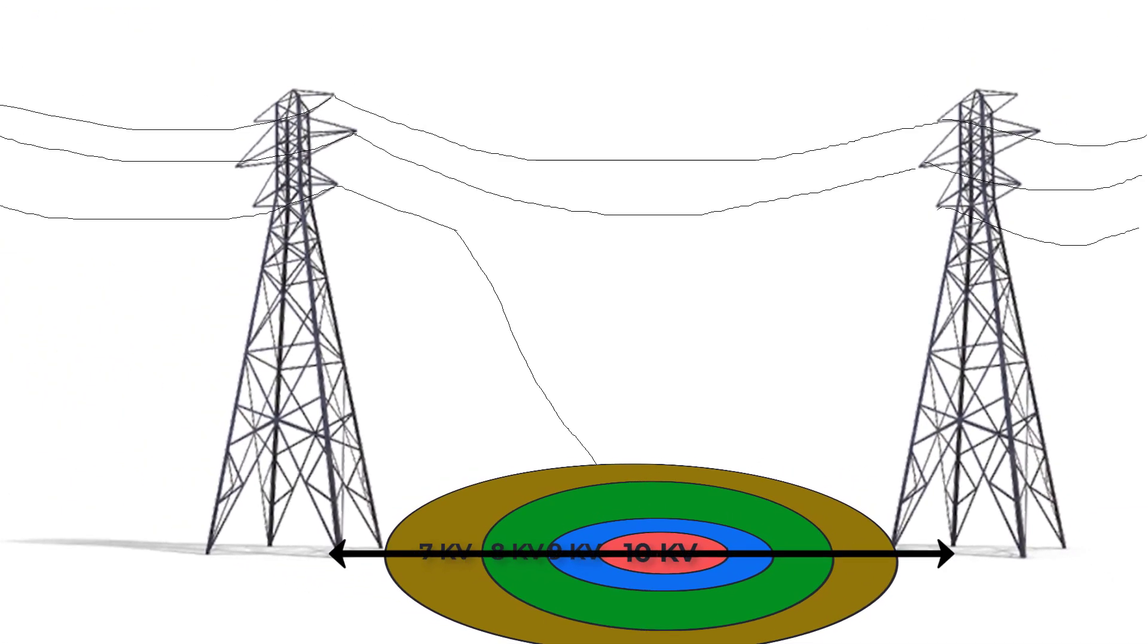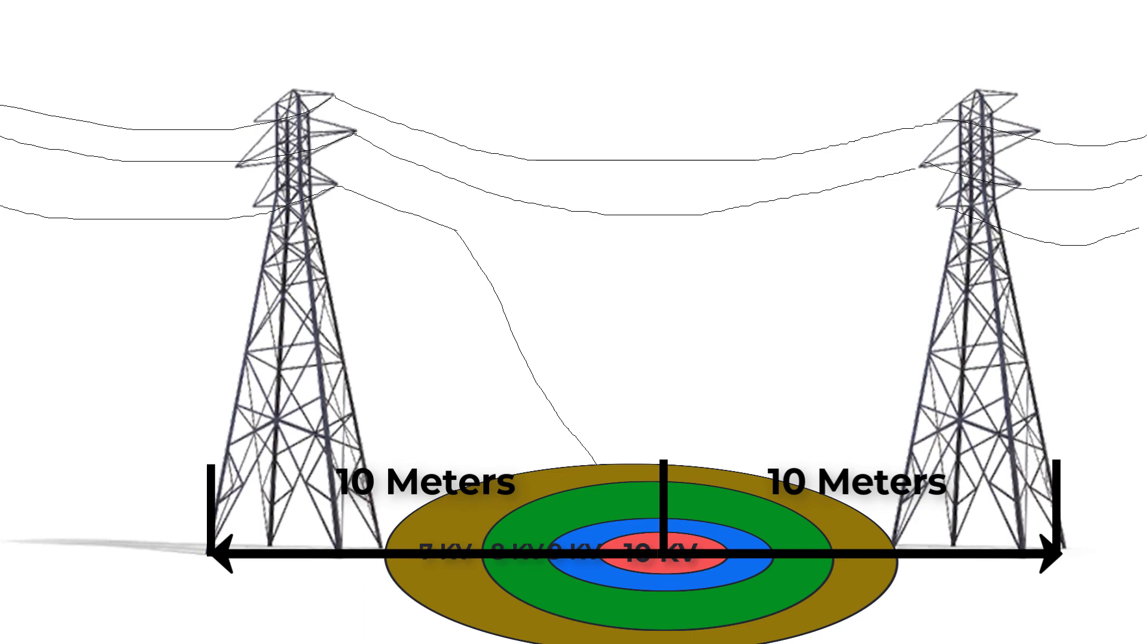Let's take an example here. Consider that the potential at the touching point due to fault is 10 kilovolt. So the other circles will equal 9 kilovolt, 8 kilovolt, 7 kilovolt and so on, until we get out of the faulted area, which is approximately 10 meters or more from the center of the fault.